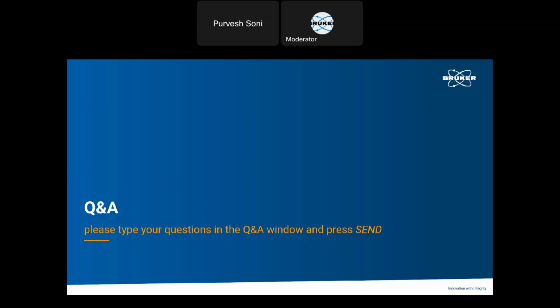The first question, I think it was asked when Purvesh started with the examples. I think you already partly answered it, but maybe just for a recap: how do you deal with sample topography? I'm talking about the first application example, the pharma sample, for instance. With sample topography, we are measuring all around the sample with the 4-segment design. So imagine having 4 EDS detectors on all sides of your chamber, and because you are measuring from all the sides, you don't miss any signal if there is shadowing or topography in the material. An easy way to look at this is that if you have a topographic material and you are shining light from all the sides, then you will not have any shadowing. So it's a similar analogy. You can measure from all 4 sides, and then you have no shadowing or topography.